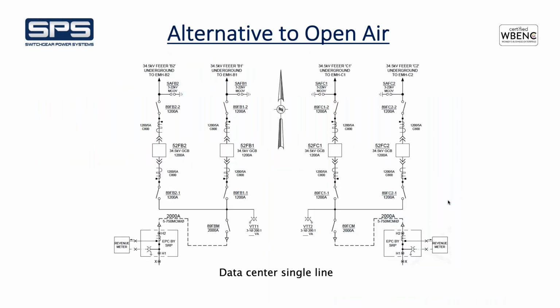So this is an example of a data center single line, and the hash marks on the breakers are actually not correct. I don't know why those are on there. But anyways, this was the single line provided to us. And this is a customer of ours. We have the purchase order to do the engineering for this project, but this customer placed a large value on utilizing switchgear rather than building the substation open air, which historically is what they would have done.